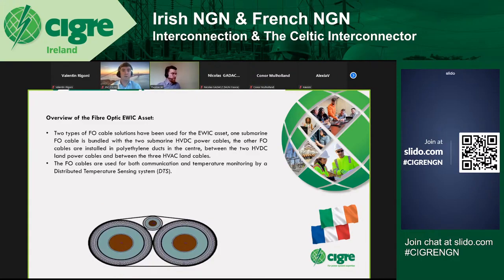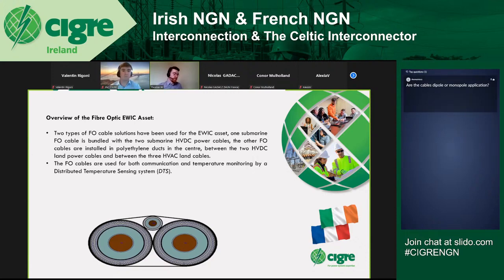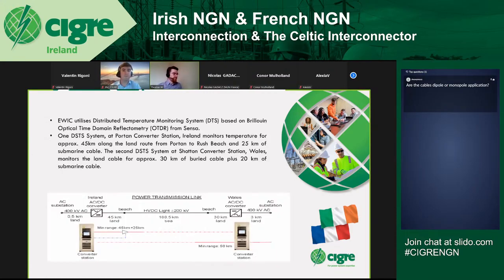As well as the power cable asset, we also run a fiber optic cable. This runs along the HVDC power cable route, installed in polyethylene ducts between the two land power cables and between the HVAC land cables also. Some of these fibers are leased externally, but for our own use we use them for communication between the converter stations, and also for temperature monitoring with our distributed temperature monitoring system, or DTS system.